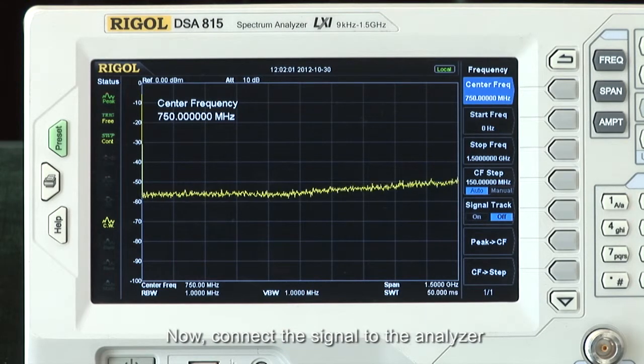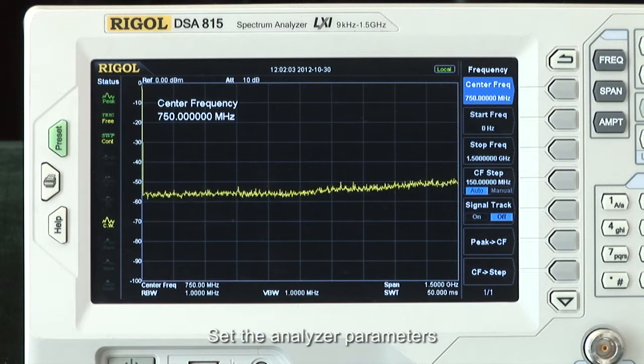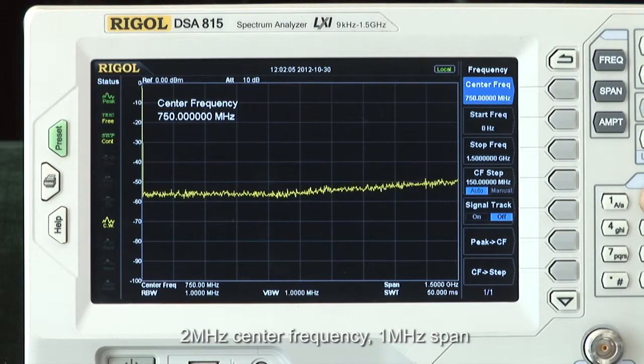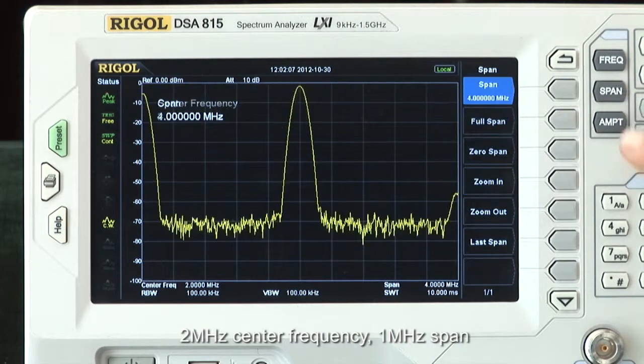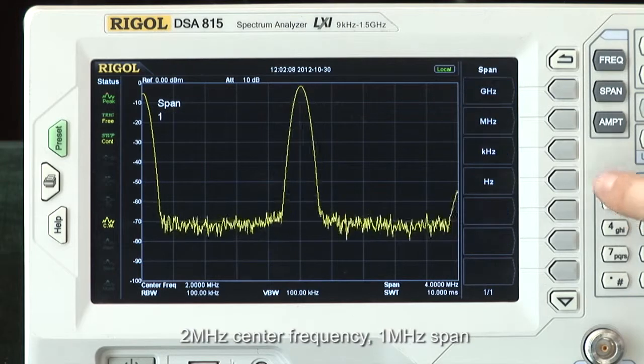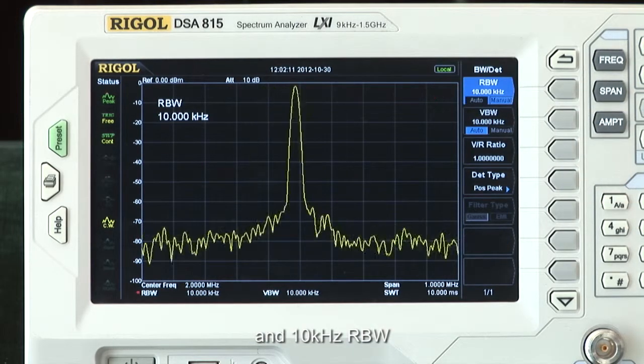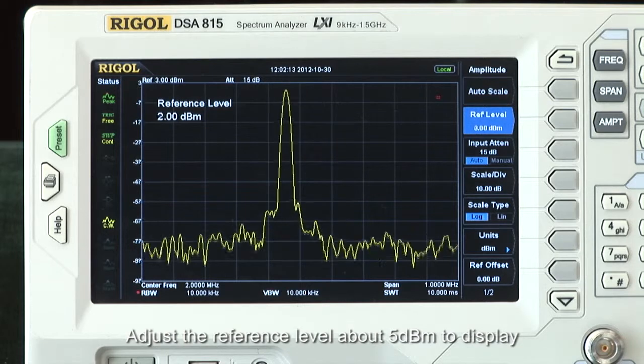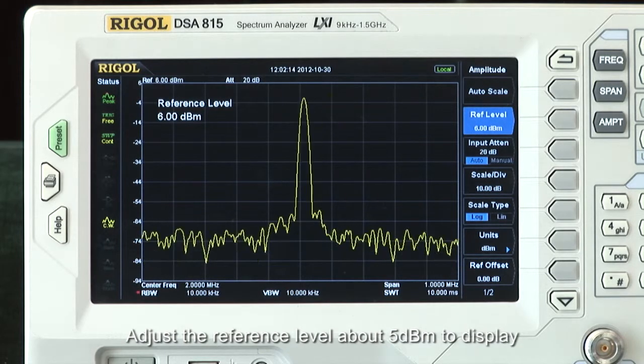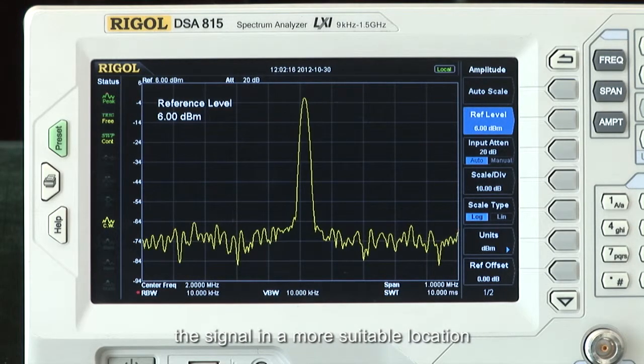Now let's connect the signal to the analyzer. Set the analyzer parameters for 2 MHz center frequency, 1 MHz span, and 10 kHz resolution bandwidth. Adjust the reference level to about 5 dBm to display the signal in a more suitable location.